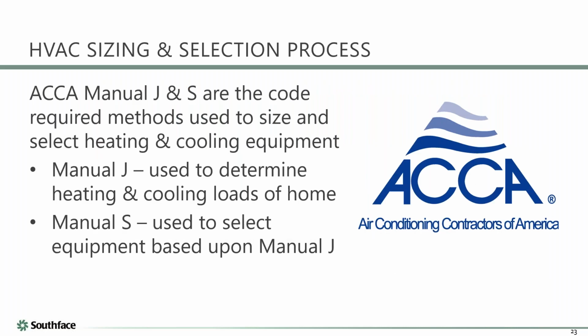However, there is a process: ACCA Manual J, ACCA Manual S. There's an ACCA Manual D for duct design, and we thought we'd just fairly quickly say Manual J is used to calculate the cooling and heating loads. Manual S is the process by which we select an actual air conditioner that will deliver the goods. It will be able to satisfy both the sensible load and the latent load.